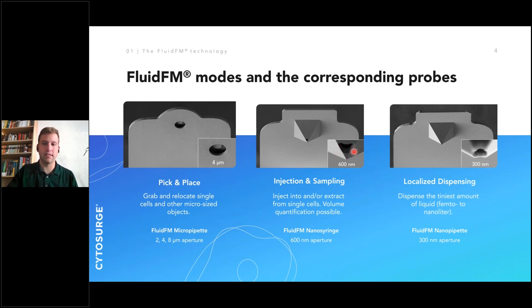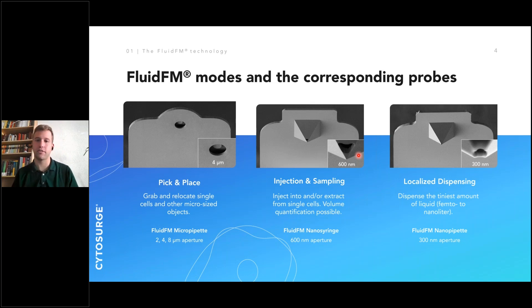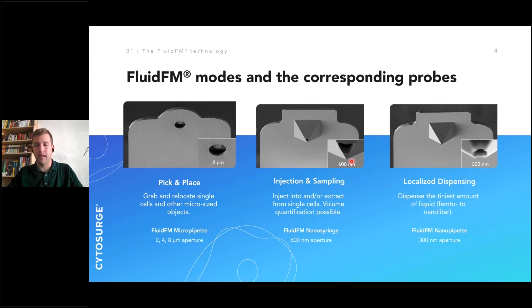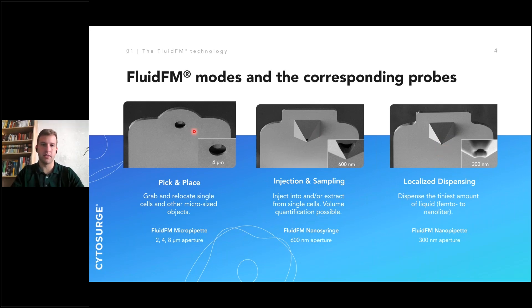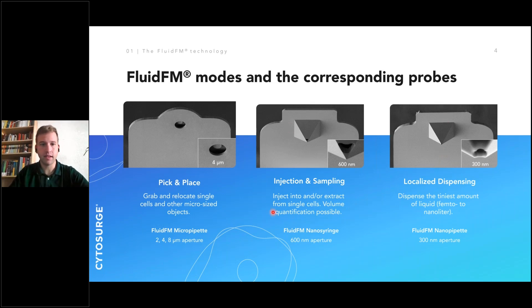Once we pierce the cell's membrane, this aperture — about 600 nanometers in its largest dimension — is inside the cell. We can then use positive pressure to deposit material into the cell, or negative pressure to take samples from the cell. The first is an injection and the second is single cell biopsy. We also have FluidFM nanopipettes, which combine both: a pyramidal tip similar to the nanosyringe but with the aperture at the very tip of the pyramid, suited for picking up bacteria or creating surface patterns.